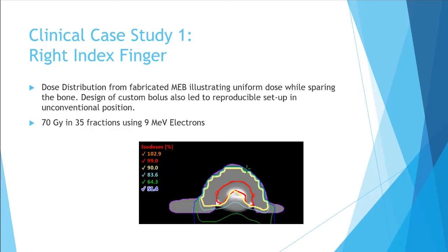So here you can see the final dose distribution that was delivered by our modulated bolus. Even though a finger is quite thin and you might think that 6 MeV electrons would be sufficient, we ended up having to move to 9 MeV electrons, mostly due to the depth of the PTV on the sides of the finger, without making the dose too hot proximally. So this prescription was delivering 70 gray in 35 fractions using 9 MeV electrons.